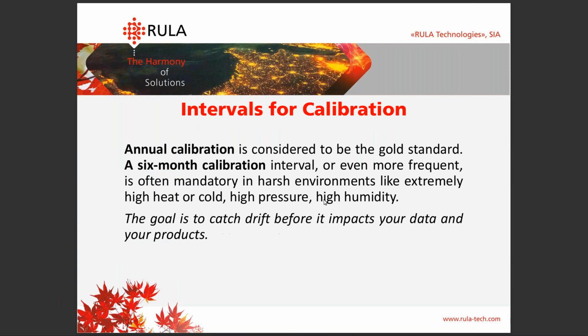We're often asked how frequently does one need to calibrate their accelerometer or their device, and it's not a trivial question because, as you know, annual calibration is considered the gold standard. However, if you're working in some extreme environments like heat or cold or high pressure, or there are some peculiarities to your process, you may want to calibrate every 6 months, or even more often, just to make sure that you catch the drift of accuracy before it impacts your data. So unless you have a specific standard in your enterprise, you want to observe your process, and you just want to make sure the data does not drift. So maybe 6 months is even better than annually.